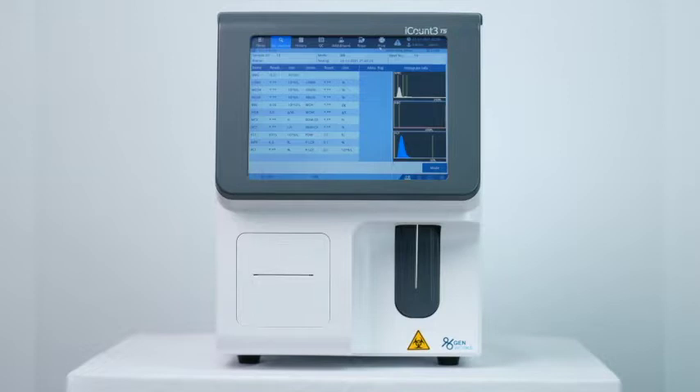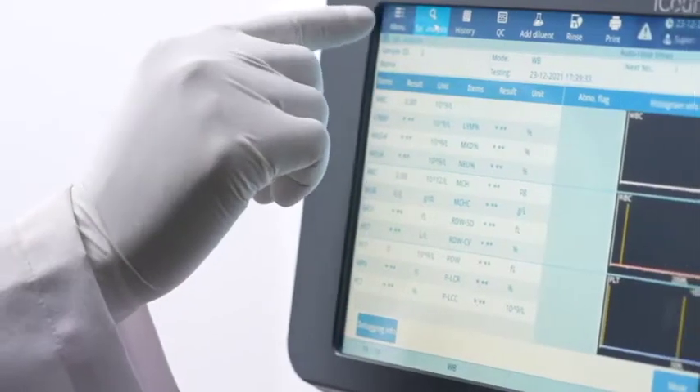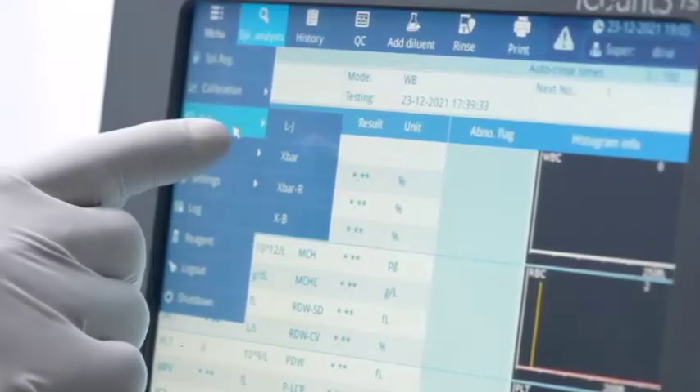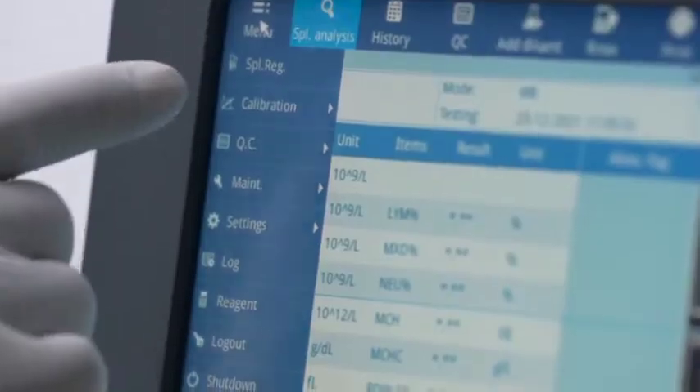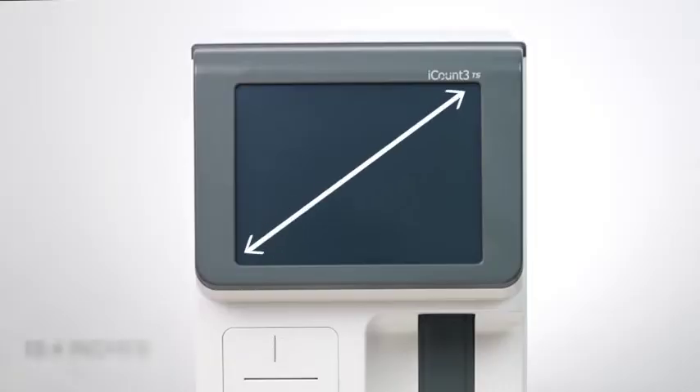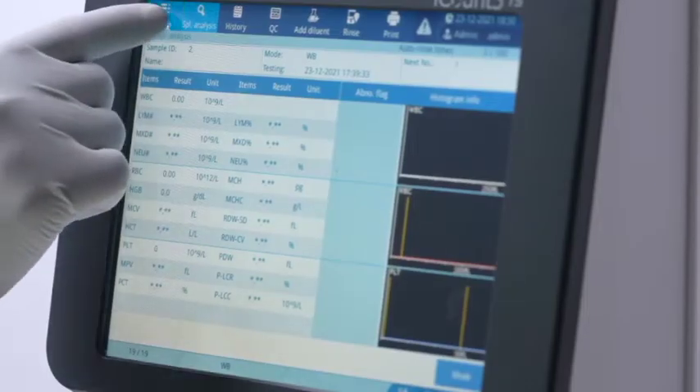Has high linearity for critical parameters like RBC, WBC, platelets, and hemoglobin. Has three levels of controls for daily quality control with Levey-Jennings charts. Comes with high ease of use — a large 10.4-inch TFT screen to display all parameters and histograms, with large buttons and an intuitive menu.